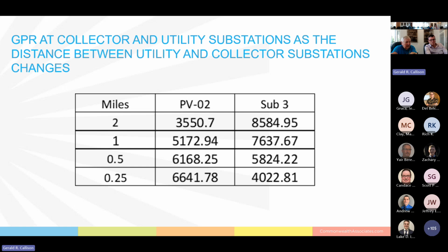So what's the ground potential rise at the collector station and at the utility as you move the two substations closer together? Well, PV2 is the collector station and sub 3 is the ground grid at the utility. So you can see that at the utility, the ground potential rise is approximately 8,600, and it's a little over 3,500 at the collector station. But if you move the utility closer to the collector station, as you can see, the voltage at the utility actually goes down, and at the collector station it goes up.